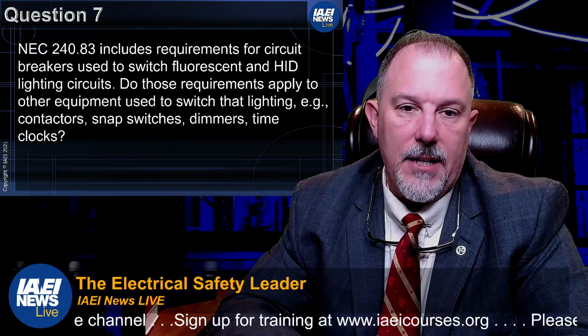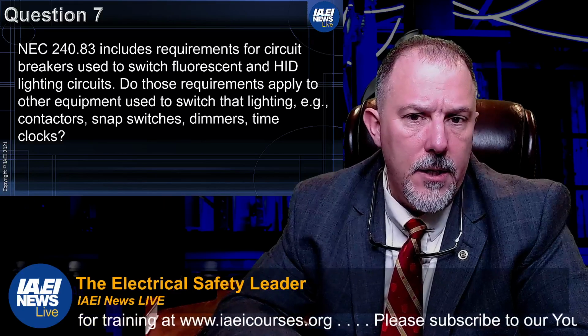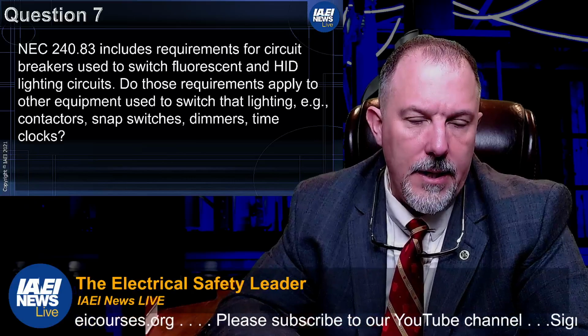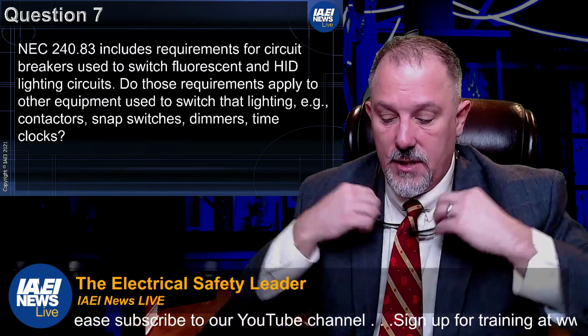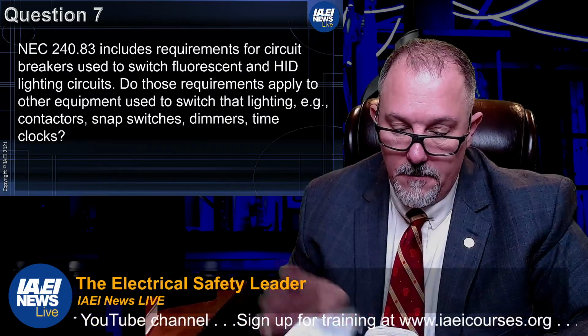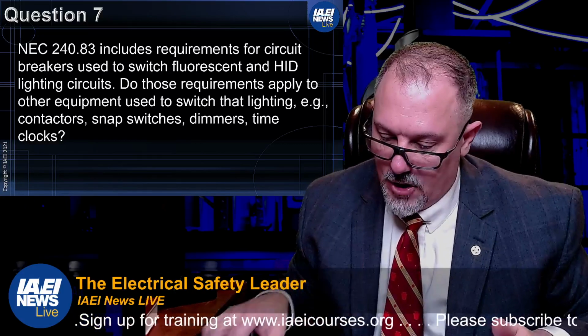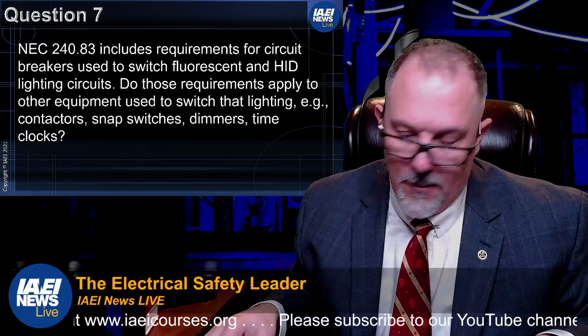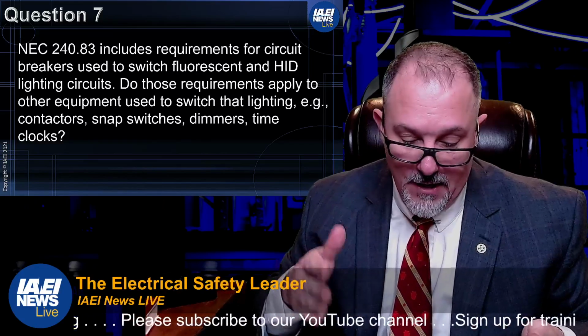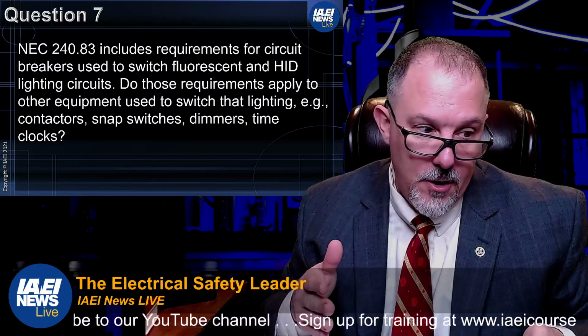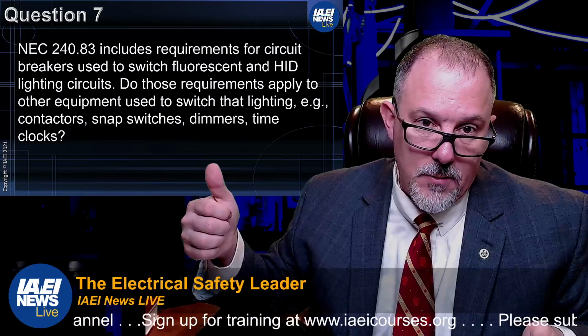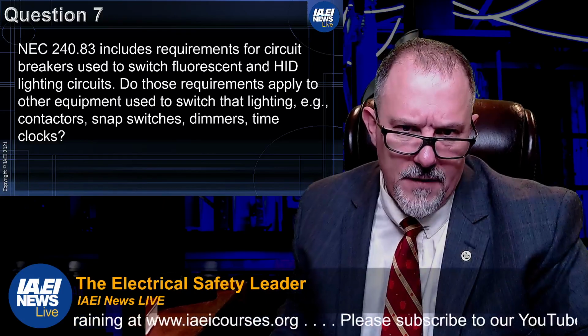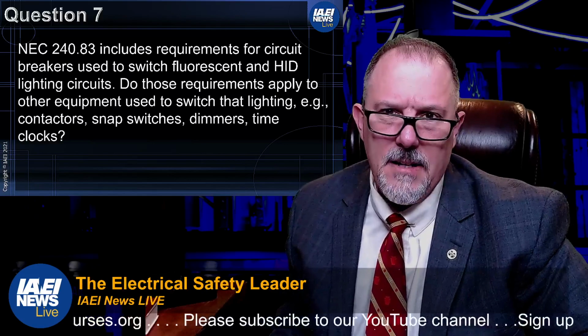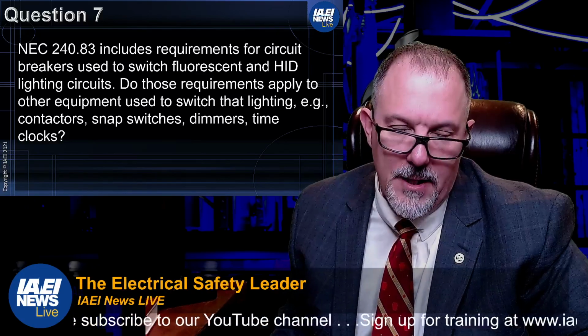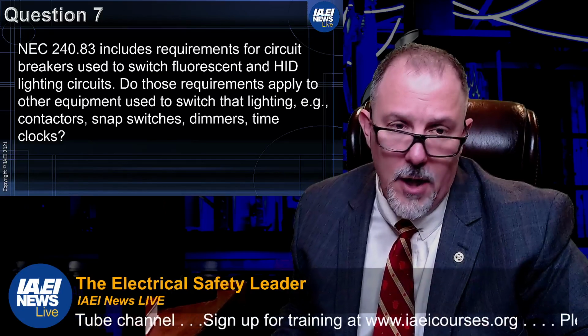So I would say that the requirements in 240.83 don't apply to other equipment because 240.83 is on overcurrent protection. If you are interested to understand the requirements for a light switch or those types of technologies, then that would be following, at a minimum, the manufacturer's instructions for the proper application of those technologies, whether it be a snap switch or dimmer switch. Snap switches are snap switches. That's just an on-off. When you start getting into dimmers, things that may have compatibility concerns, you're going to want to reference the manufacturer's instructions. But remember, Article 240 is overcurrent protection. Hopefully that helped a little bit.